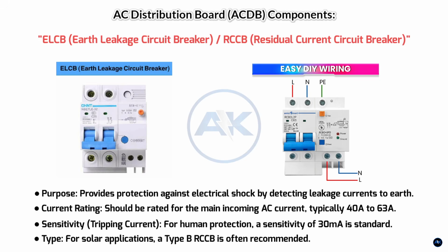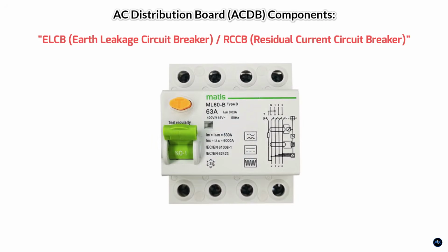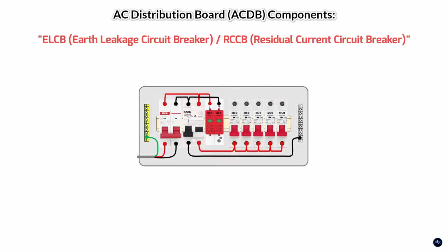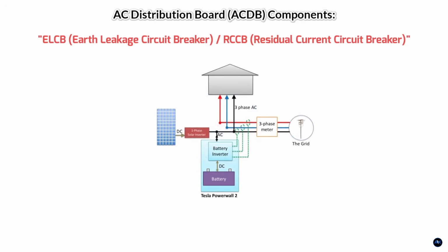This is because solar inverters can sometimes produce DC leakage currents, which a standard type A or AC RCCB might not detect, making them unsafe. Type B RCCBs are designed to detect both AC and pulsating smooth DC leakage currents. Placement: usually placed at the main incoming supply point in the ACDB or your home's main distribution board. Some hybrid inverters have built-in RCD functionality.